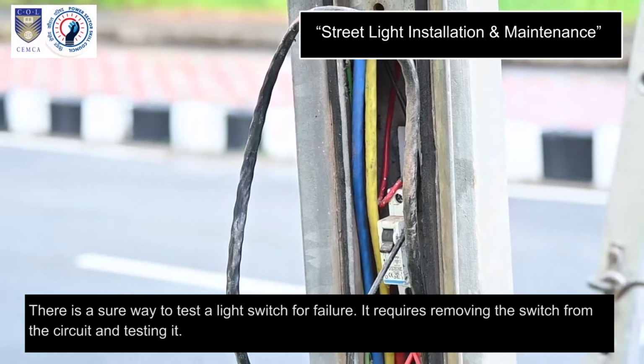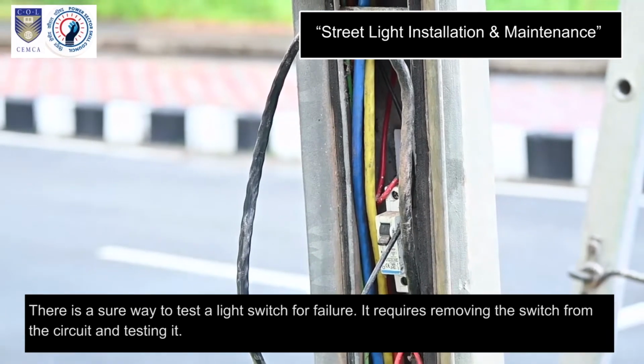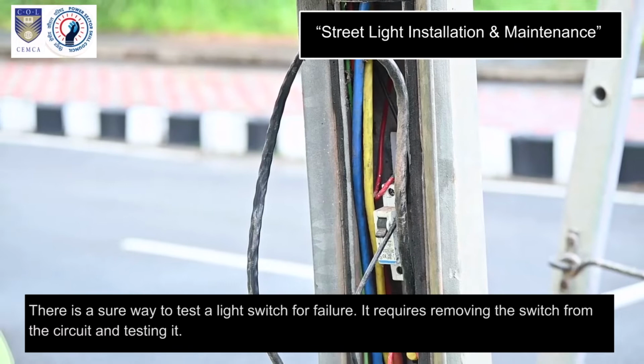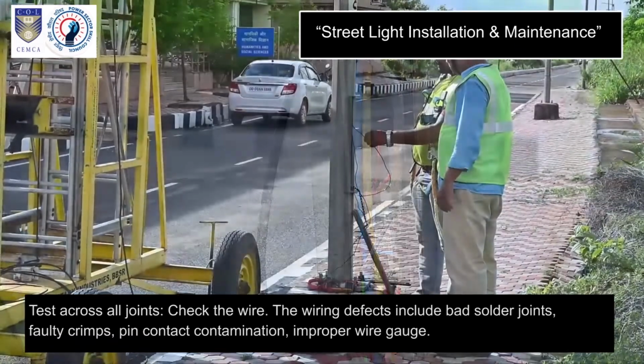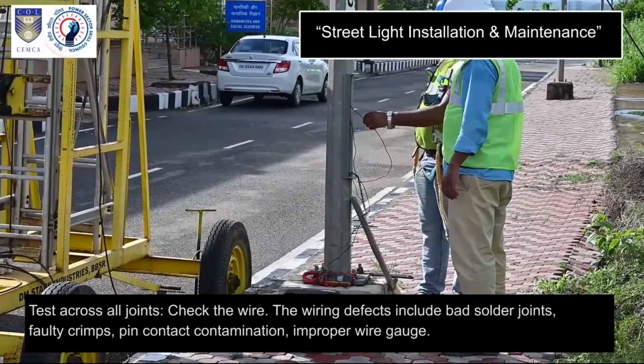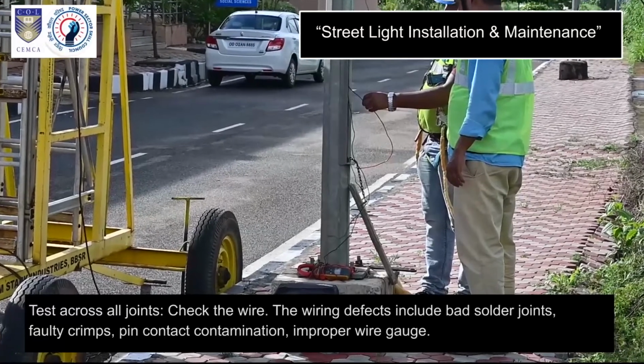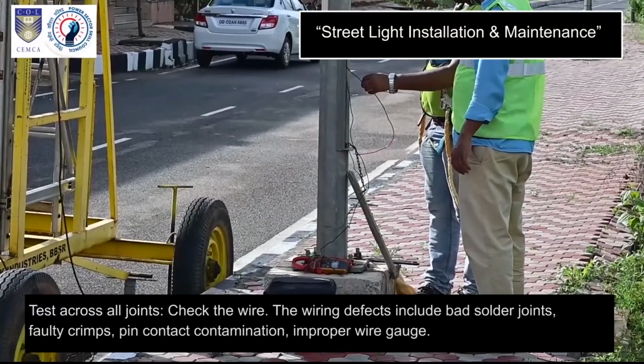There is a sure way to test a light switch for failure. It requires removing the switch from the circuit and testing it. Test across all joints. Check the wire. The wiring defects include bad solder joints, faulty crimps, pin contact contamination, improper wire gauge.